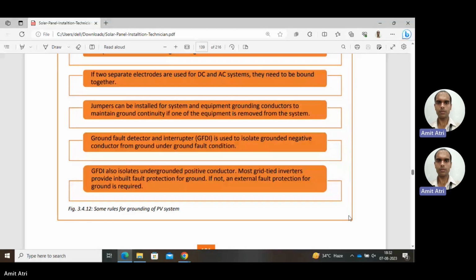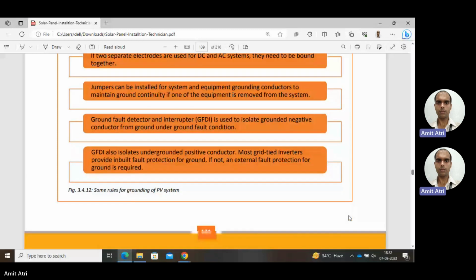The next rule is the ground fault detector and interrupter, GFDI for short. The ground fault detector and interrupter is used to isolate the grounded negative conductor from ground under a ground fault condition, because a ground fault could also occur if the grounding is not proper. For that we need a detector and interrupter. The GFDI also isolates the ungrounded positive conductor. Most grid tie inverters provide inbuilt ground fault protection, which is an advantage of grid tied inverters. If not, an external ground fault protection is required. If the inverter is not providing this facility, then we need external fault protection for the grounding. Okay, so here we shall stop now.